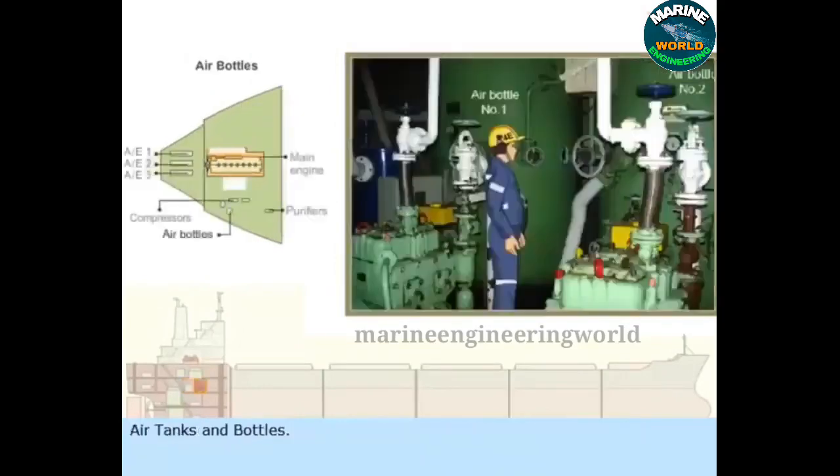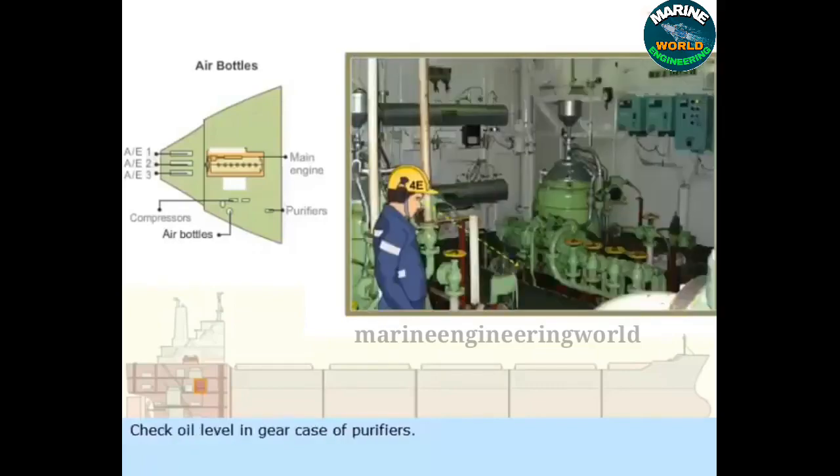Air tanks and bottles. Check bottle pressure. Drain bottles till all the water is removed. Check oil level in gear case of purifiers. Check back pressure of purifiers which are running. Check oil temperatures at inlet to purifiers. Check amperage. Check for abnormal noise.